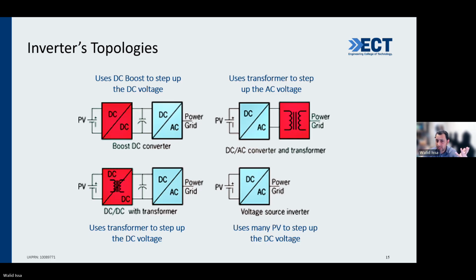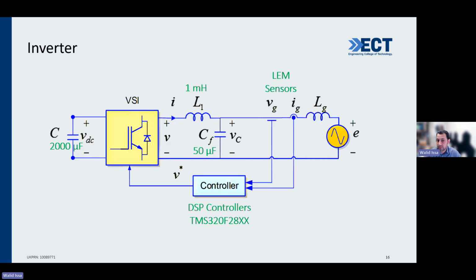Another option: you don't have low voltage at all, you already have 800 or 700 volt by stacking series panels or batteries, and you can convert it straight away, DC to AC, as is. So these are examples of how the inverter integrates sources into the grid: one uses a boost converter, one uses a transformer, another uses a transformer to step up DC to DC, so that one is DC to DC while the other is AC to AC. The last one uses many PV panels stacked to step up the voltage directly before conversion.